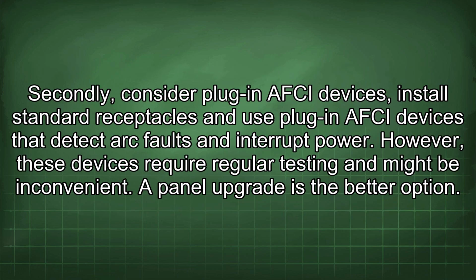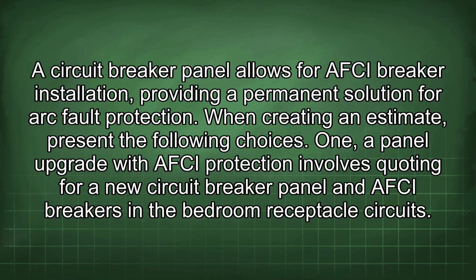Secondly, consider plug-in AFCI devices. Install standard receptacles and use plug-in AFCI devices that detect arc faults and interrupt power. However, these devices require regular testing and might be inconvenient. A panel upgrade is the better option. A circuit breaker panel allows for AFCI breaker installation, providing a permanent solution for arc fault protection.